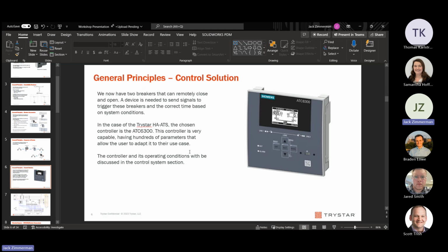So this device effectively takes in signals that we choose it to take in, whether it's voltage, frequency, those kind of things, and it makes decisions to activate different accessories on the breaker, whether it's a shunt trip, the closing coil, those kind of things. As well as that, it can activate annunciators for errors.